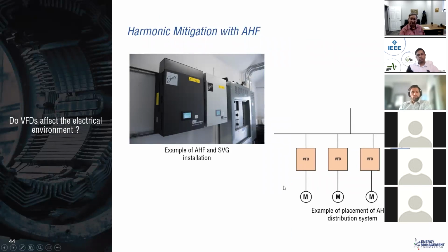Sometimes these active harmonic devices can be the least expensive solution. Here you see a couple of units mounted on the wall. These are in parallel, so you have to remember the beauty of this is you're not putting all of that current in series. You're not having to process that whole 600 amps. We have 100 amps of injection here. And if you have a lead, a lag, and a standby, you don't have harmonic filters on each of those. You've got one device, and we do a lot of those applications that make a lot of economic sense.